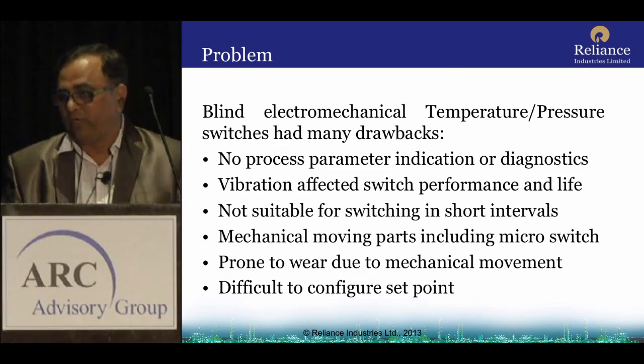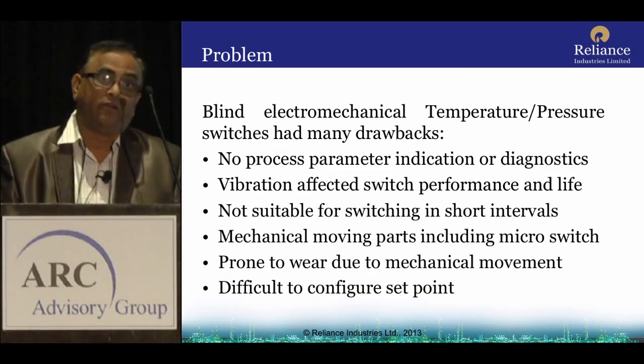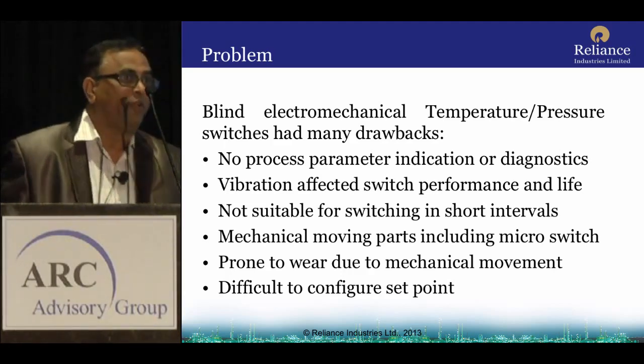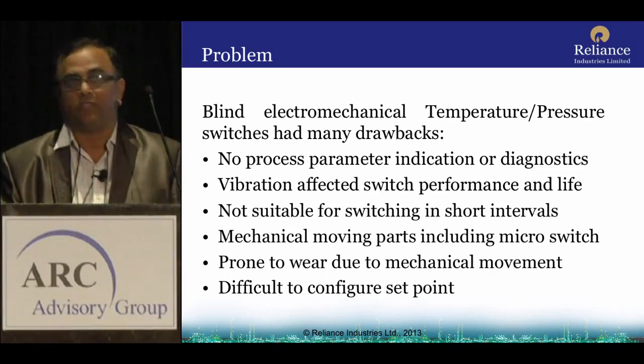Set point drift requires routine recalibration and deadband setting of any electromechanical switch, either a temperature switch or a pressure switch.